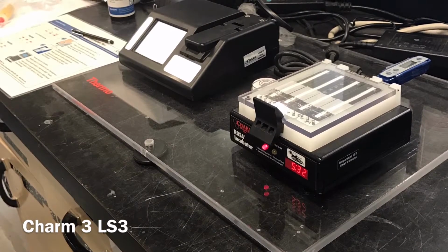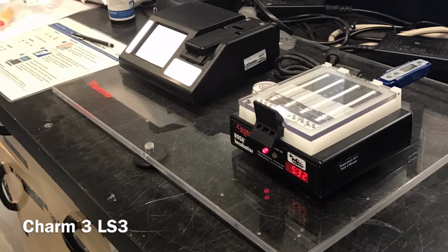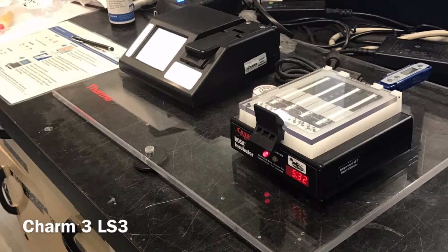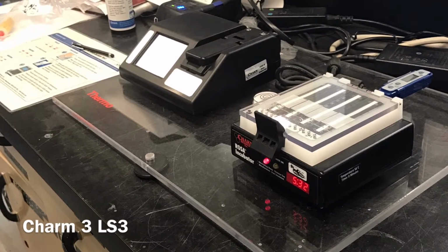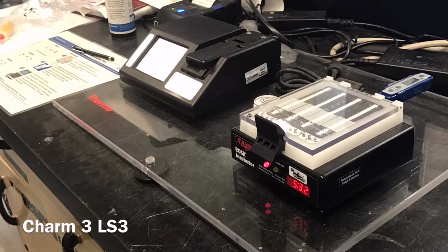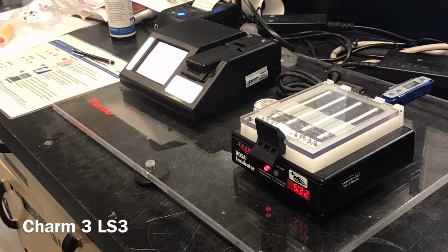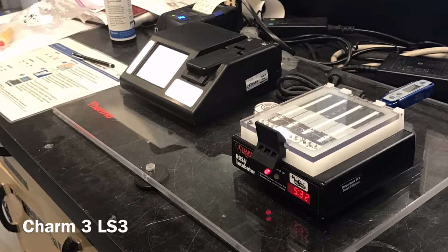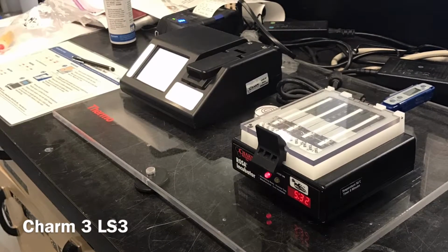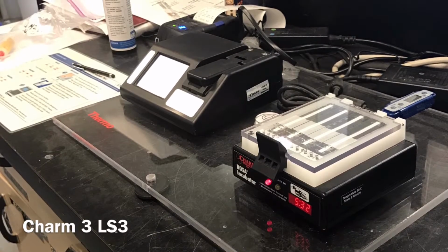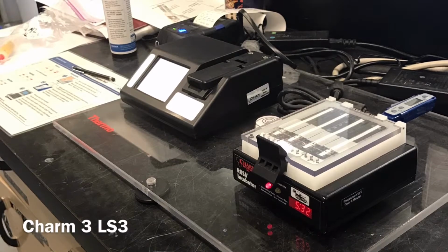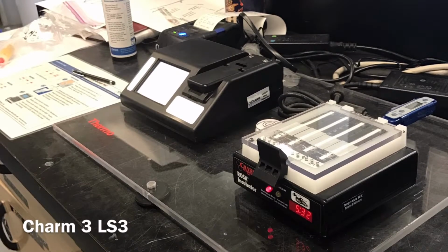It is important to calibrate the positive control as the positive rating and the negative control as the negative rating. If they are incorrectly calibrated, a sample of milk that needs to be tested may generate an incorrect reading. This can result in accepting milk that has the presence of antibiotics or rejecting milk that has no presence of antibiotics.